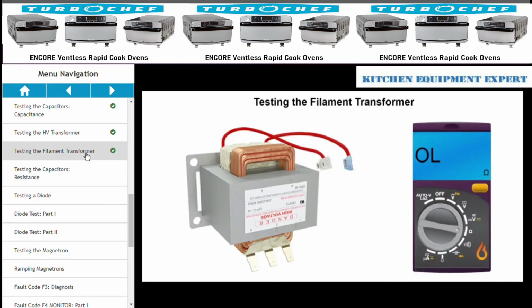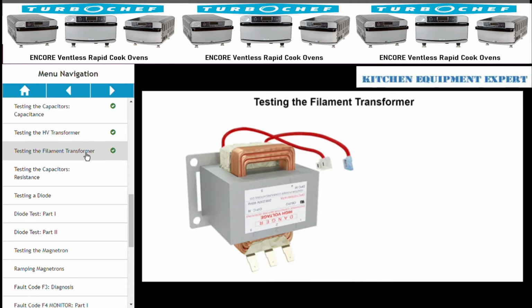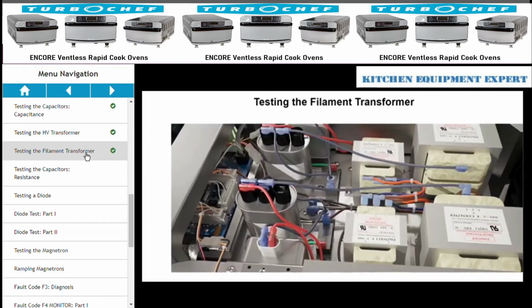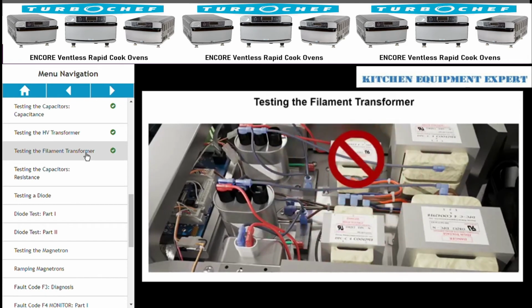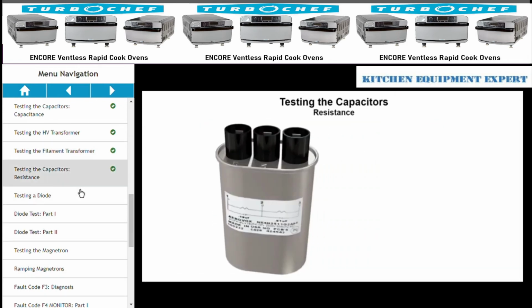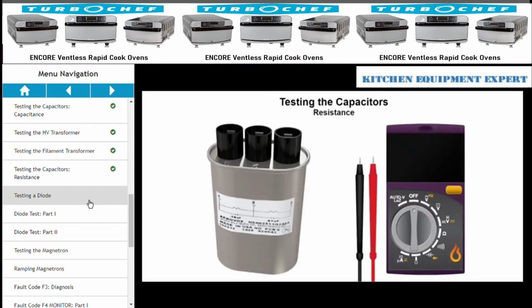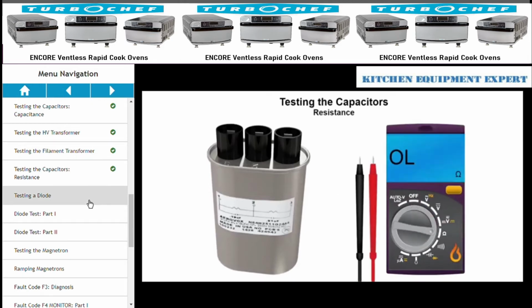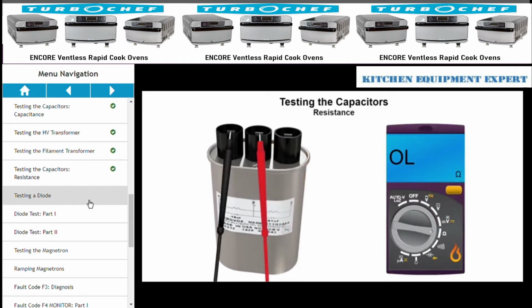With your meter on the ohm scale, measure between 4 and 5. You should see very low resistance. If you see an open circuit, the transformer is bad. You can also test a capacitor with the ohm scale on your multimeter. Set your multimeter to the ohm scale. Test between any two terminals.